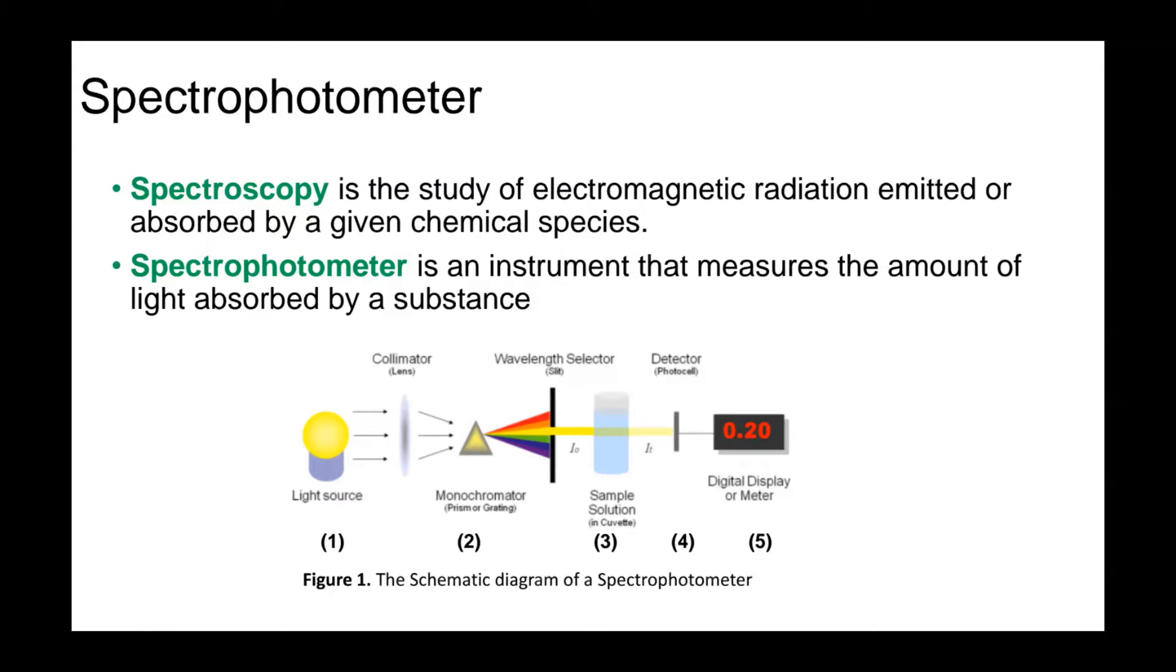A light source is capable of providing a range of wavelengths. A monochromator selects a particular wavelength of light and delivers this to the sample cell with an original intensity I₀. The sample cell contains the solution in a cuvette or test tube which is being analyzed. A detector measures the intensity of the transmitted light from the sample. And a digital display or meter displays the transmitted intensity.